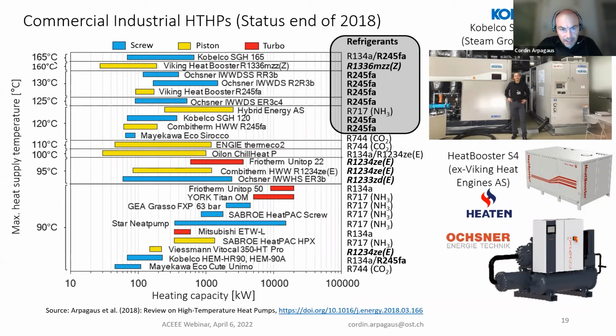You can see numbers from ACEEE and so on. R245FA, for example, is a hydrofluorocarbon which has quite a high global warming potential, close to 1000 times that of CO2. That means it needs to be replaced in the future due to regulations, and that's an active research area too - these refrigerants and the alternatives for them.